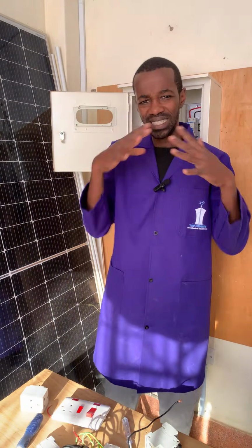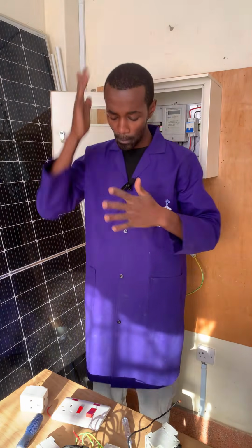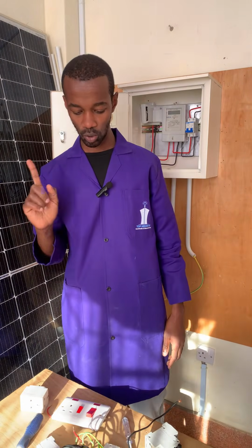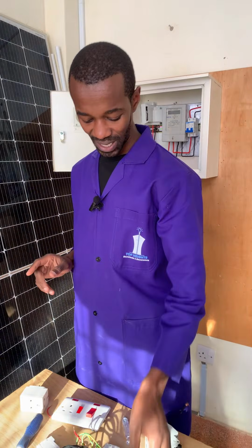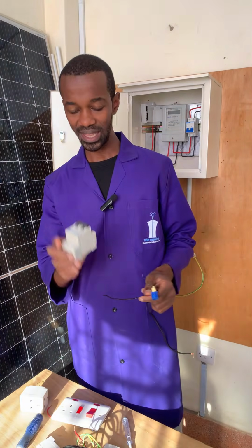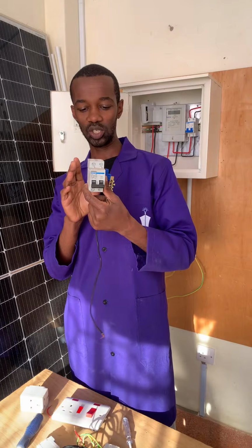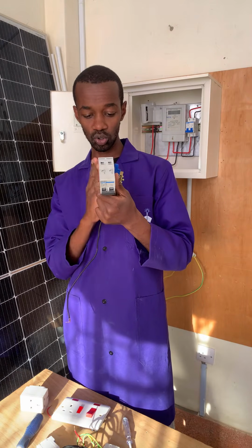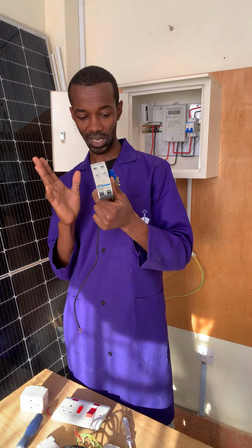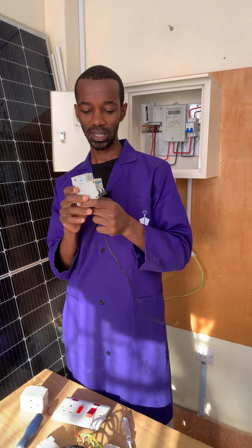When the customer says that, as an electrician, just know there could be a loose connection. So the first target is definitely on the main switches, and your target should be on the neutral. If there's a loose neutral, a loose connection somewhere, just know that could be the reason.